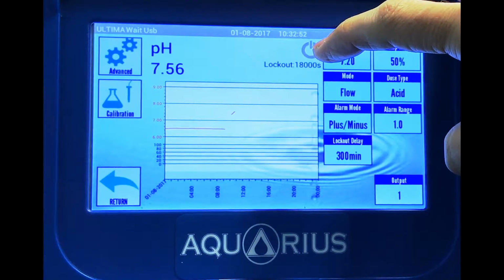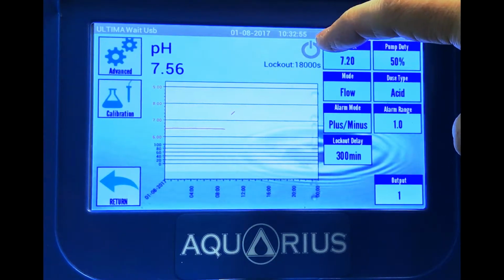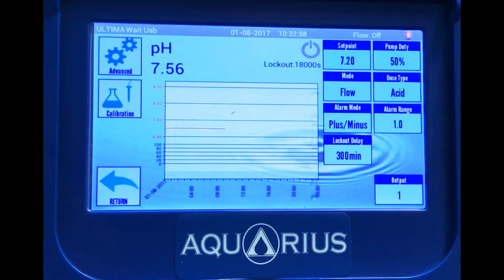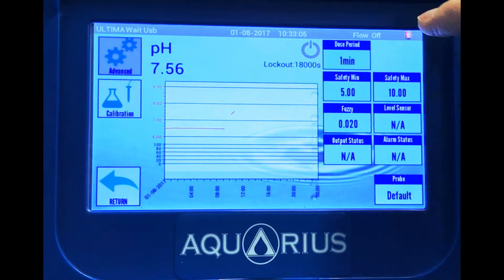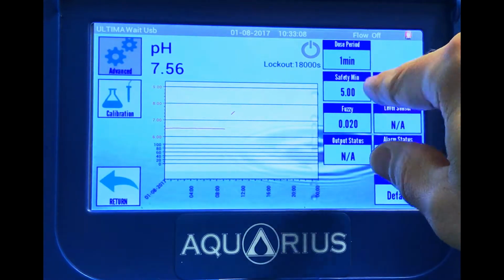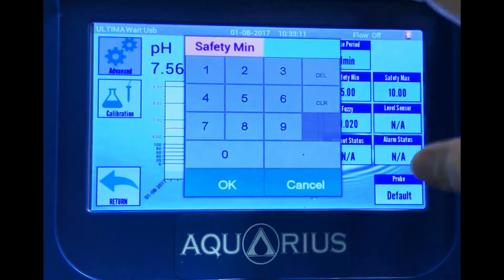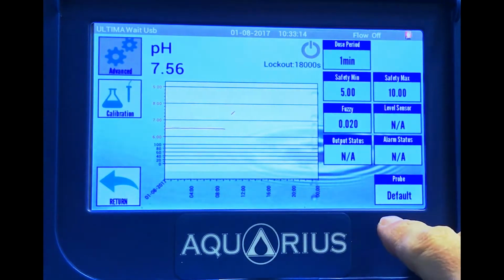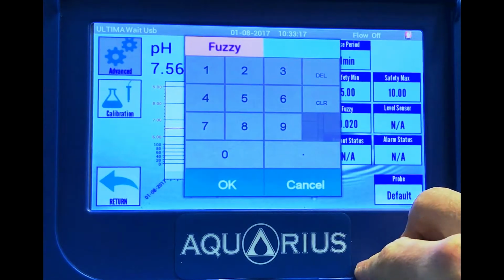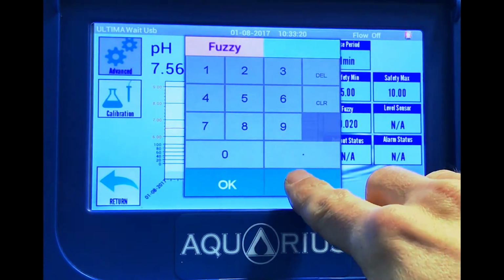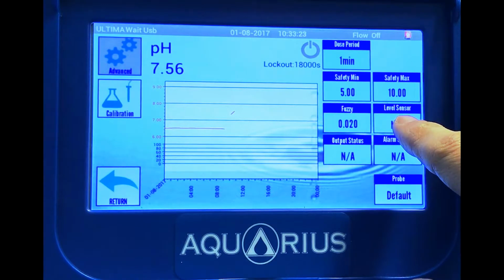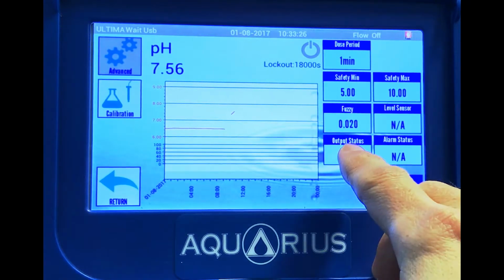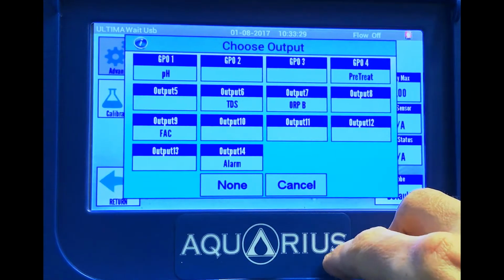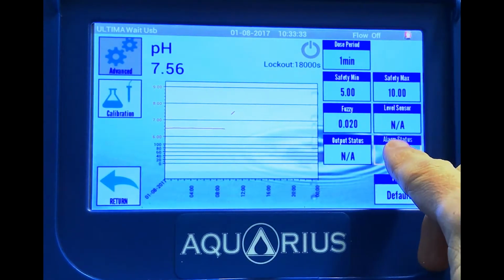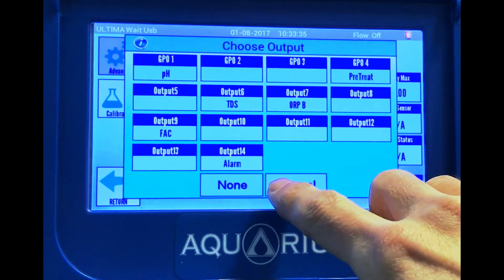The power icon up here is grey when the output is off and blue when the output is on. Advanced gives you options to change dose period, safety minimum and maximum, which are only related to timers if you have a timer set. Fuzzy logic gives you the option to change the proportional dosing. It gives you an option to add level sensors and to dose off other outputs simultaneously, and also to connect an alarm status from this output.